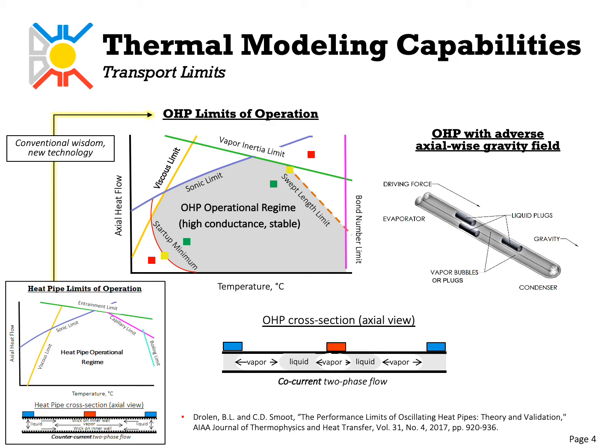The model used for the limits development is a simple force balance on the liquid slug or chain of liquid slugs. I started with envisioning the things that could break down the slug. I see the slugs as pistons that are driven by the pressure head behind them. When the piston breaks down, say into an annulus, the pressure head has greater difficulty in driving the flow since the vapor can slip by the liquid.